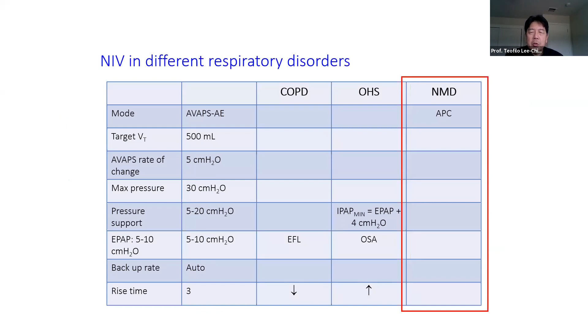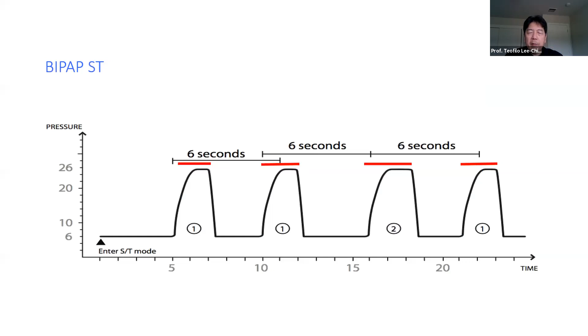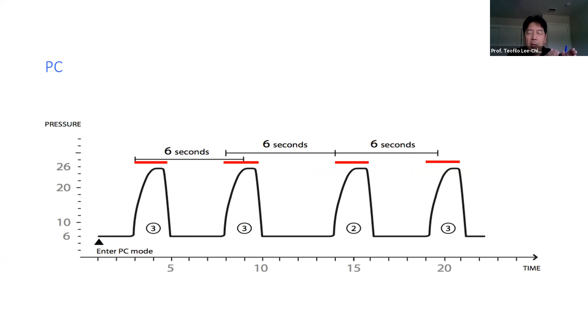Finally, in neuromuscular disorders, they have difficulty maintaining inspiration. So if you see, for instance, with the BiPAP ST mode in a person with neuromuscular disorder, you will see that the inspiratory time differs from breath to breath to breath. And a pressure control mode will tend to stabilize that by maintaining an augmented breath in order to maintain a more uniform inspiratory time with each breath.